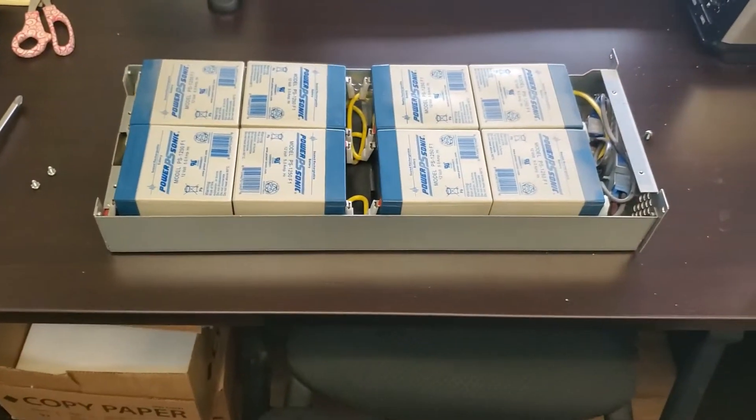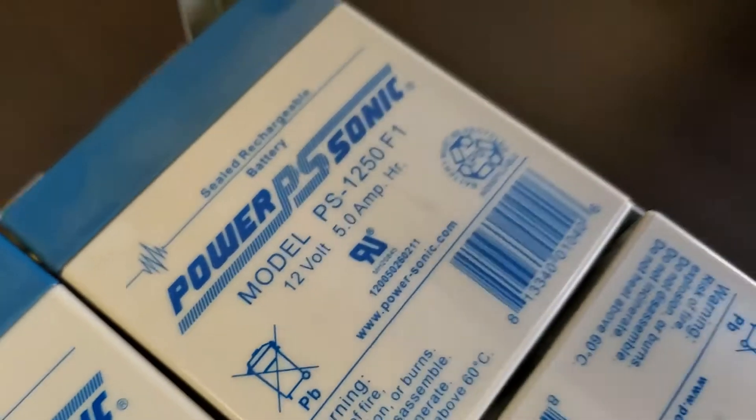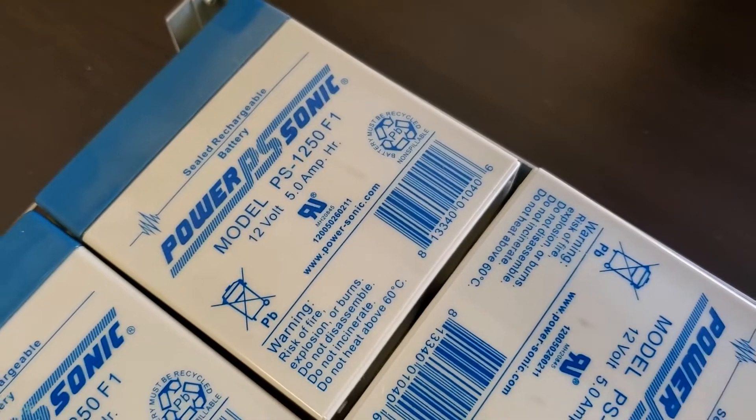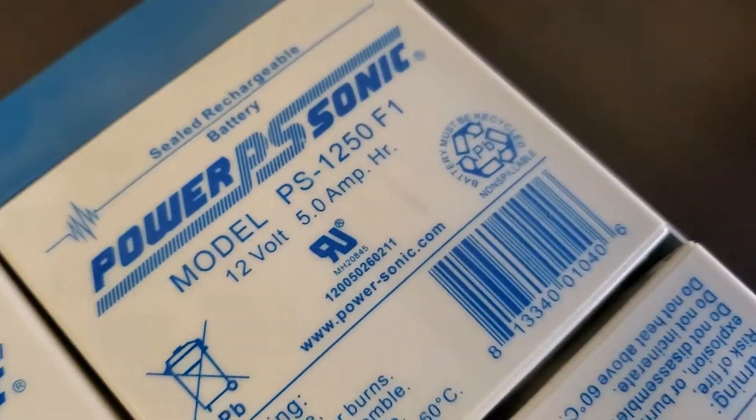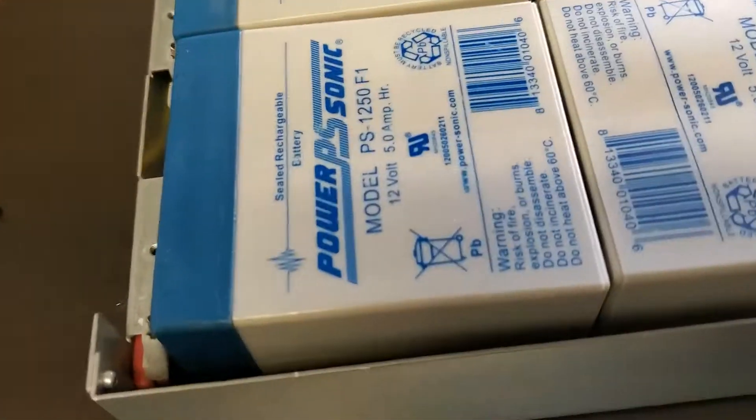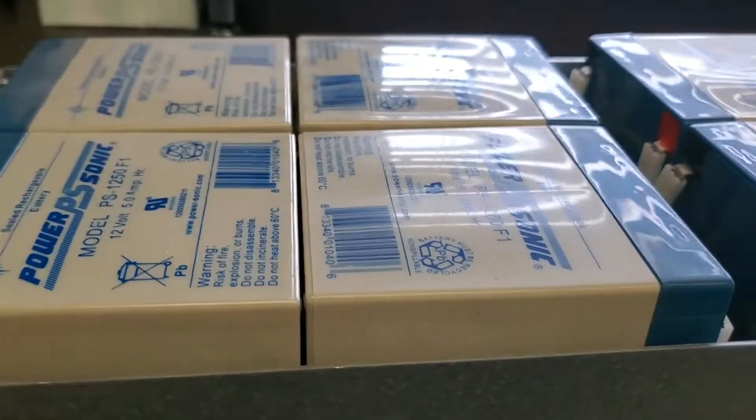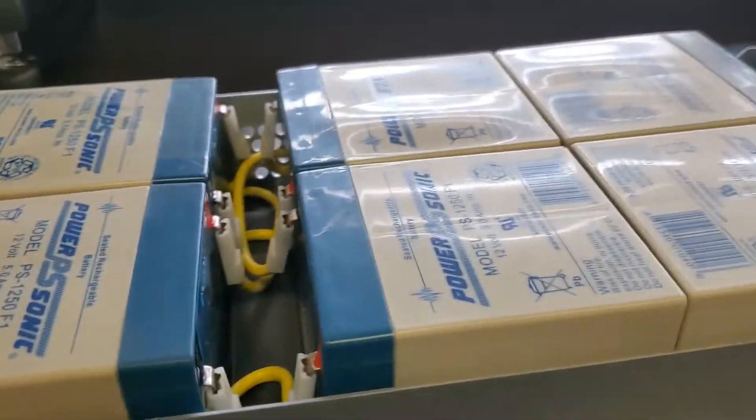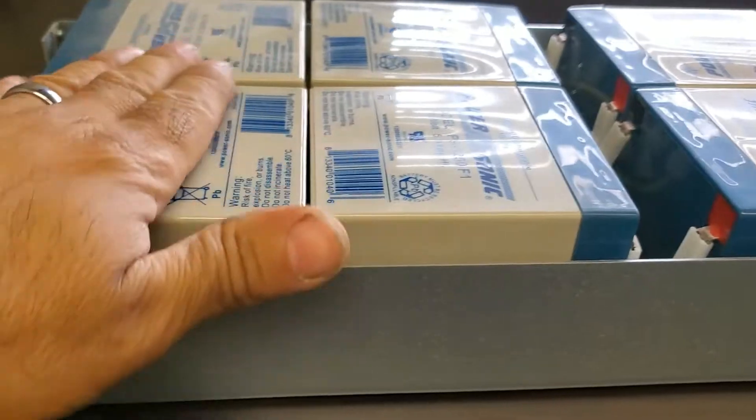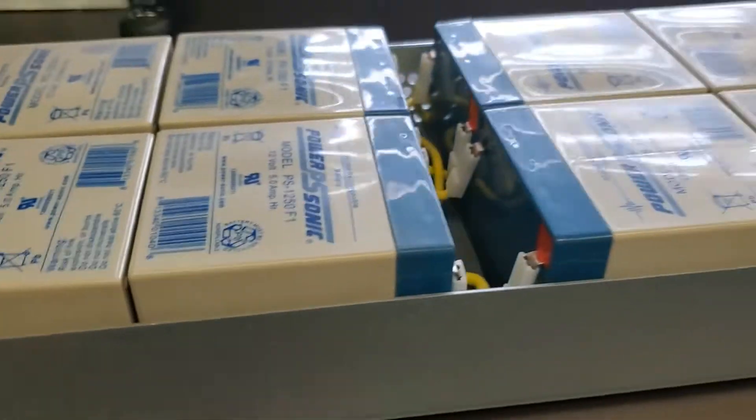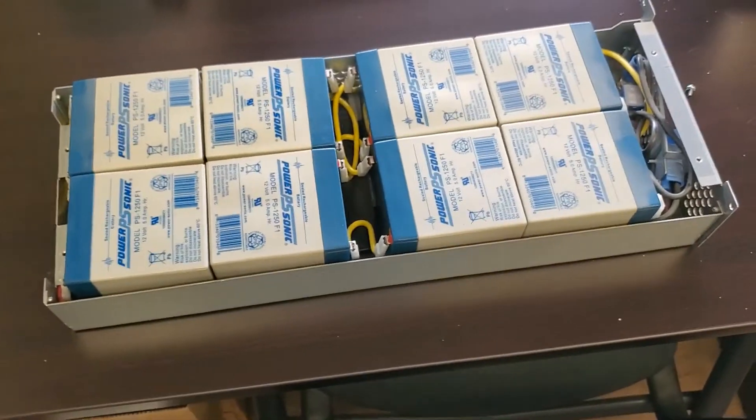You've got eight batteries. Each one is a PS-1250 F1, which just means 12 volt, 5 amp. It doesn't matter what brand, as long as they're the same size and same amperage. You can see these are a little bit bulged and a little bit warm to the touch. These need to be replaced.